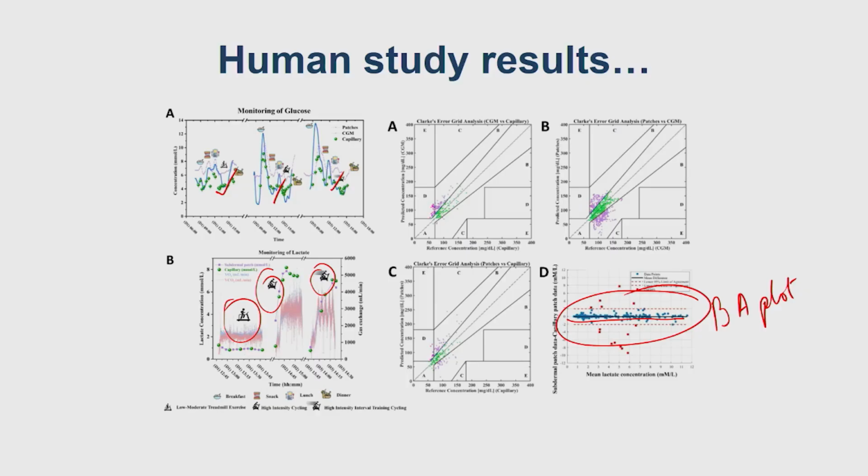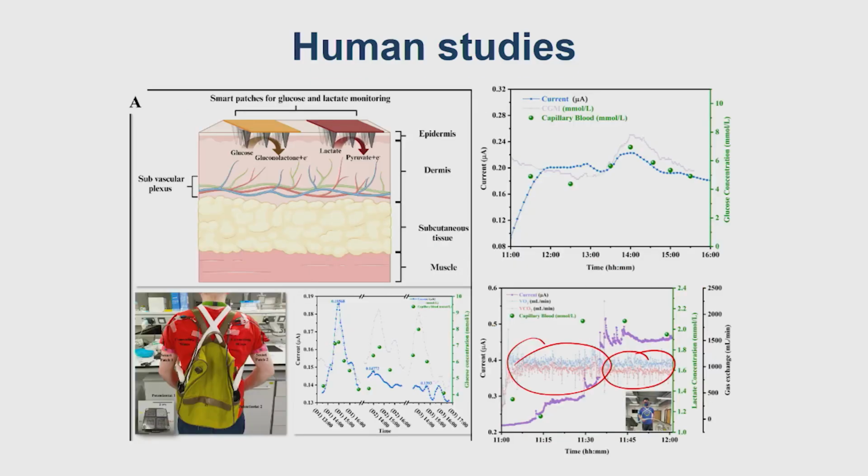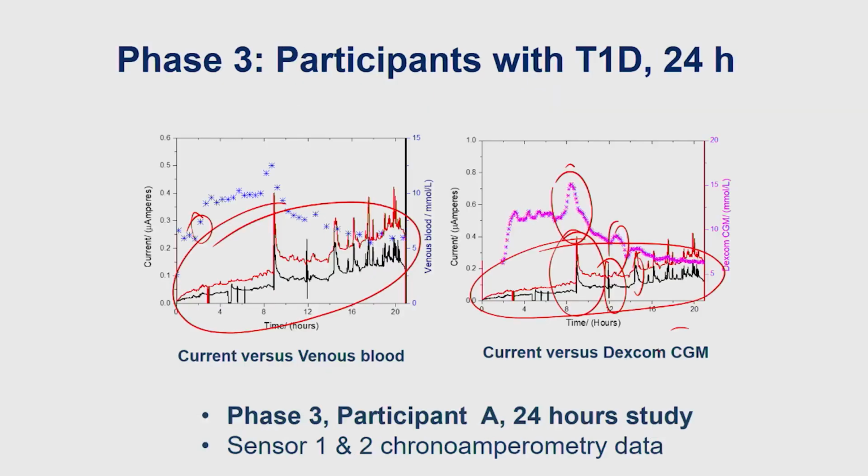And just if we go to the device comparison where you have these plots, I just wanted to ask a few things there. If you move forward. This one? No, next one. Where you have the CGM, yeah, this one. What I found quite interesting here is, if you look at the peaks, the pink, which is the Dexcom CGM sensor, it looks like there is some sort of a delay or some sort of a filter kind of response there.